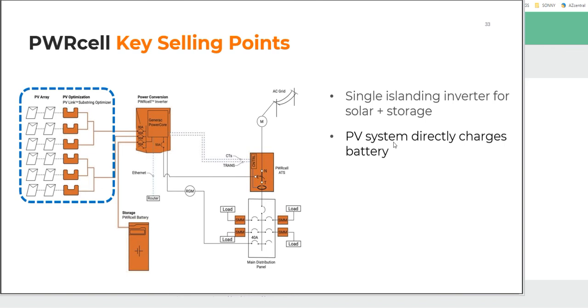The PV system directly charges the battery rather than going through the inverter. That provides a lot of benefit, not just in backup power, but also in clipped power. So if I've got a 10 kilowatt array on the roof and I'm pushing 7.6 kilowatts out through the inverter, that's all I'm ever going to deliver, either to the grid or to the battery if I'm trying to charge one. With a PWRcell, if I've got 10 kilowatts on the roof and I'm pushing 7.6 kilowatts out to the grid, the remaining 2.4 can go right into the battery. So having a DC coupled system allows you to harvest energy that would be clipped using other systems, and that's an important distinction — it's something that would be thrown away otherwise, and we put it right into the battery.